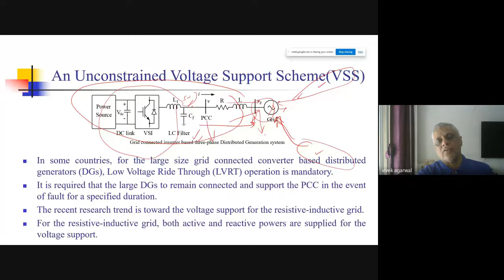But now the same thing the system will also do. So basically their generation, which was going into the grid, will suddenly stop. So even if there was no fault and it was just a false alarm, what will happen because of this? Suddenly this withdrawing its generation and cutting off from the grid, there will be a chain reaction. Other systems will also cut off.